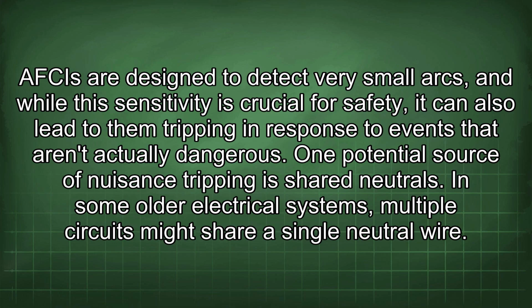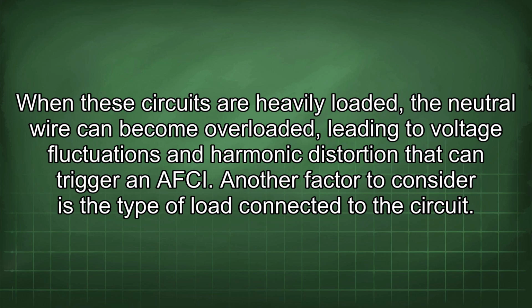One potential source of nuisance tripping is shared neutrals. In some older electrical systems, multiple circuits might share a single neutral wire. When these circuits are heavily loaded, the neutral wire can become overloaded, leading to voltage fluctuations and harmonic distortion that can trigger an AFCI. Another factor to consider is the type of load connected to the circuit.